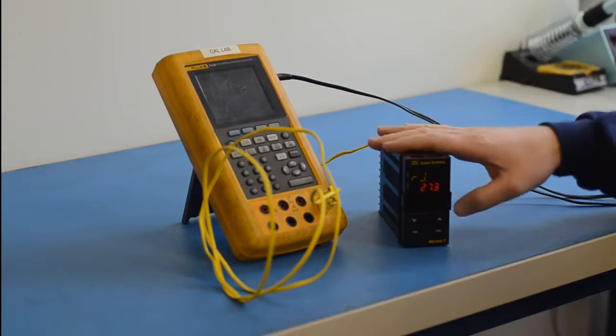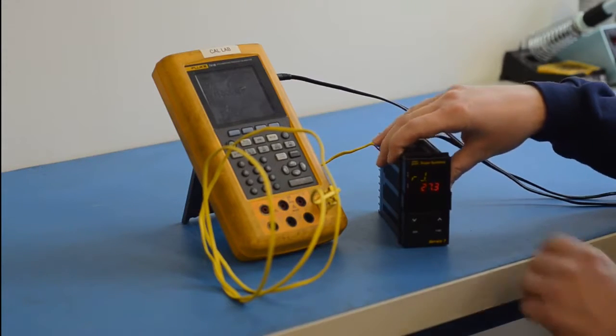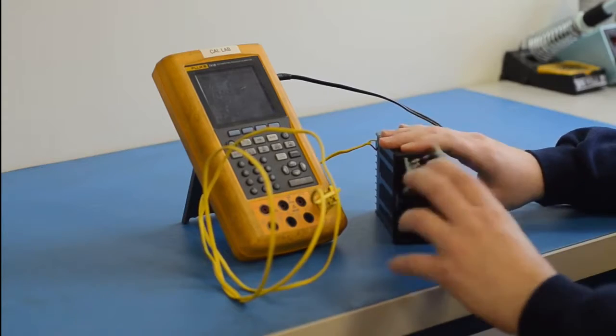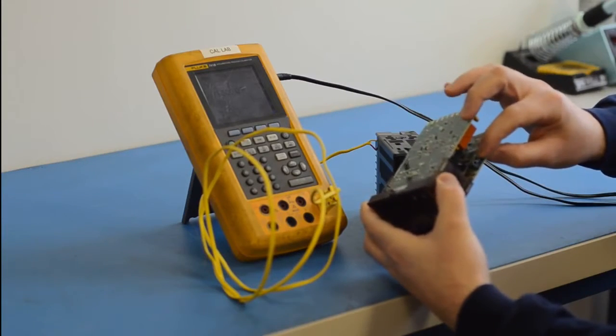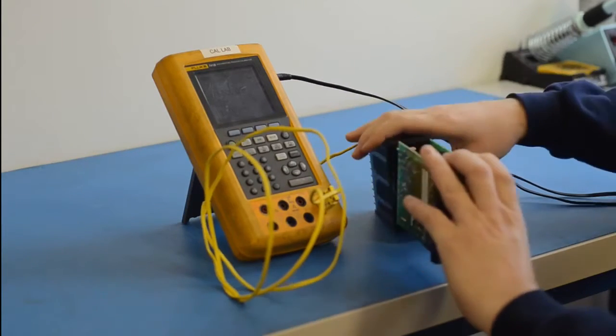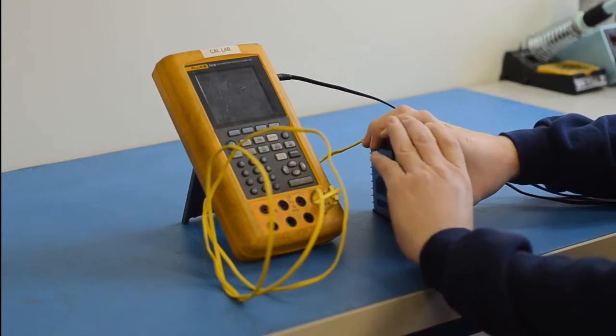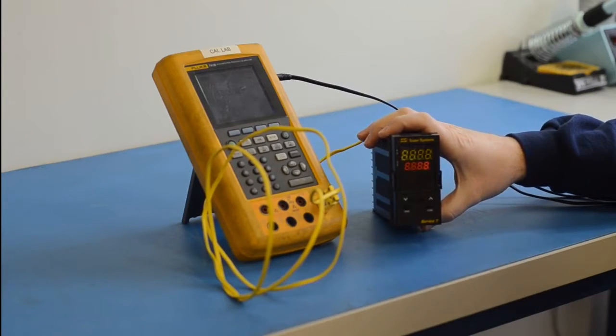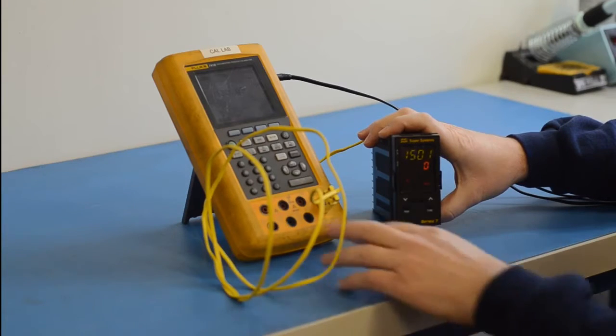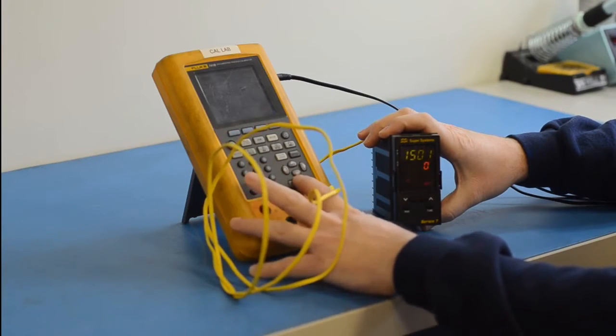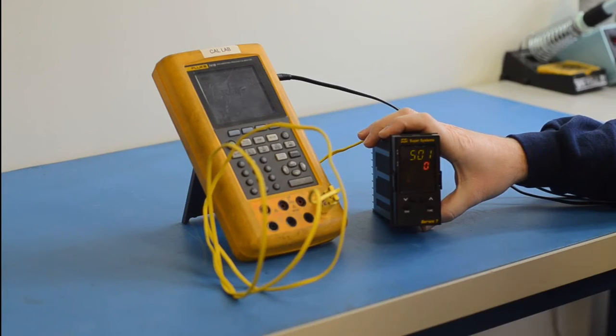After your cold junction compensation is complete, then what you will do is, for the final time, remove your instrument, relatch your jumper, insert your instrument back into its case. When it reboots and restarts here, you can see that it is within a degree, and the calibration will then be complete.